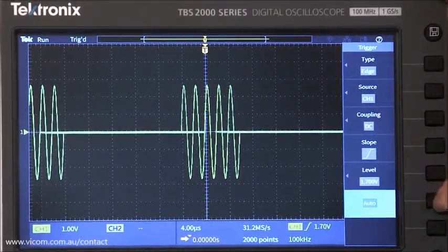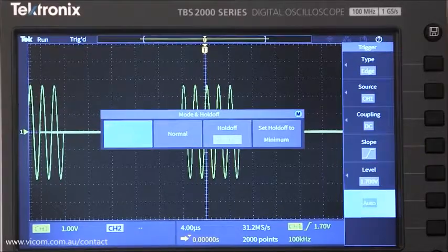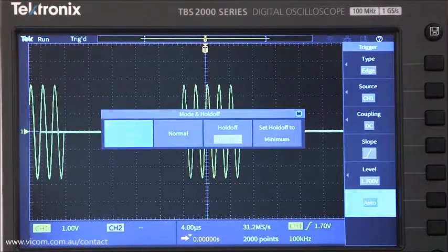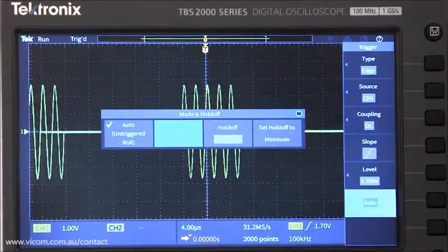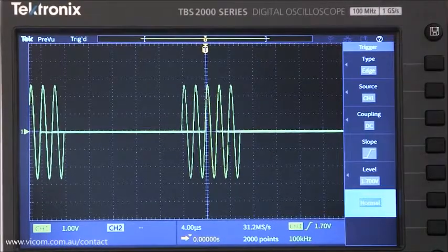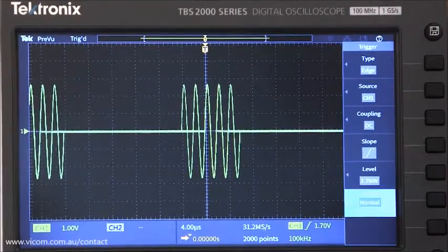The other trigger mode is normal mode. It's a little counterintuitive, but normal mode is not the default setting. When the trigger system is in normal mode, the scope acquires a waveform only when the trigger condition is met.